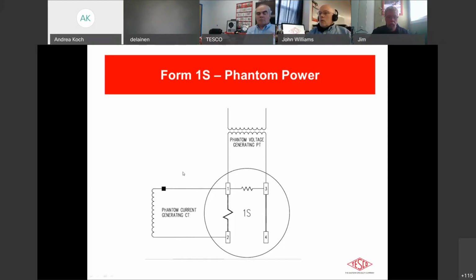Here, to create the phantom load, we have that last stage of the circuit that we talked about, which is a potential transformer. So we have that isolation here. And again, I didn't draw all the other electronics that go around the test board, but certainly for a 1S meter, you would tie your leg 3 to ground and just apply 120 volts to pin 1. The current transformer coming out of the amplifier circuit would then be wired independently from pins 1 and 2 on a 4-jaw meter, and that current would flow out of the top of the CT down through the current element and then back on the return.